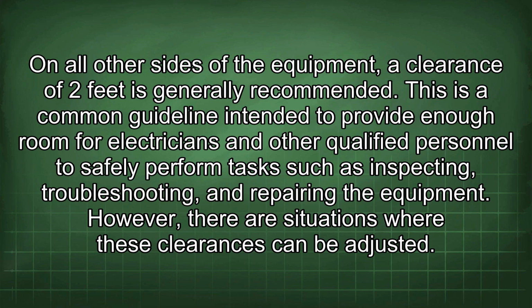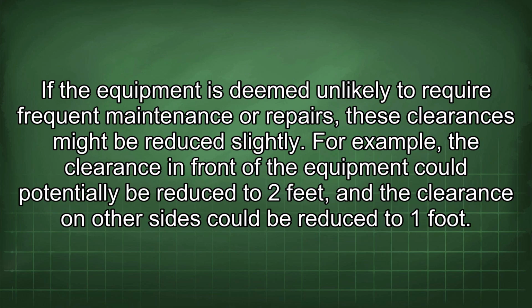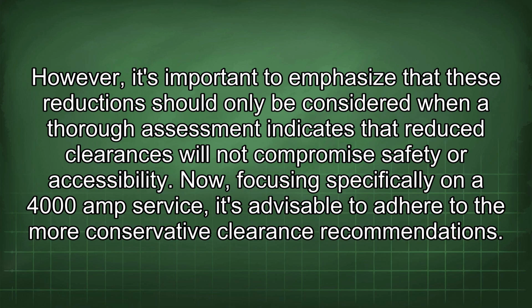However, there are situations where these clearances can be adjusted. If the equipment is deemed unlikely to require frequent maintenance or repairs, these clearances might be reduced slightly. For example, the clearance in front of the equipment could potentially be reduced to 2 feet, and the clearance on other sides could be reduced to 1 foot. However, it's important to emphasize that these reductions should only be considered when a thorough assessment indicates that reduced clearances will not compromise safety or accessibility.